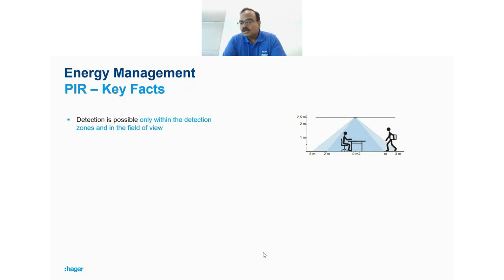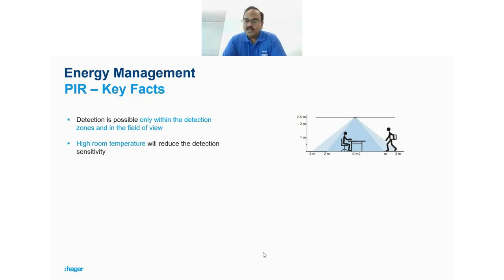Another key point: an increase in room temperature reduces the detection sensitivity. The pyroelectric sensor detects the temperature difference between the body and the room. When someone moves in, they create additional heat. If the room temperature itself is close to body temperature — meaning the difference is less — the sensor will have difficulty sensing it. Indoors, mostly air-conditioned spaces work well, but PIRs placed externally or in non-air-conditioned spaces will have reduced efficiency.